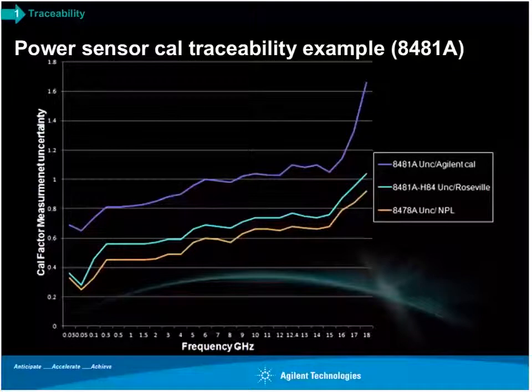If you then use that to calibrate one of the Agilent 8481 sensors, you get the next line that's just above that. And if you use the second line there to calibrate another one, then you get the line above that. In each case, you can see that the measurement uncertainty is becoming larger. So that's that unbroken chain of comparisons that we were talking about earlier on.